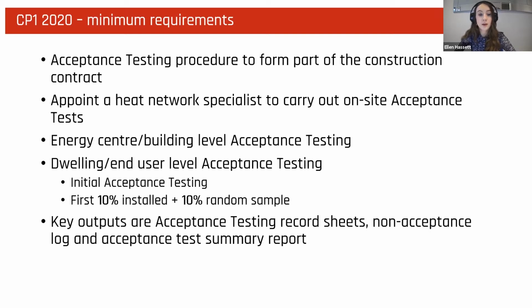And then acceptance testing of dwellings, which includes an initial set of tests on a small number of dwellings to establish systemic issues that can be rectified before commissioning and testing the rest of the development. And then taking a graduated risk-based approach to the rest of the development. So that's testing the first 10% of dwellings and then a randomized 10% sample of the remainder. And if any of those fail to meet requirements, then a further 10% should be tested, and so on. So the key outputs here are record sheets, a non-acceptance log, and a summary report.